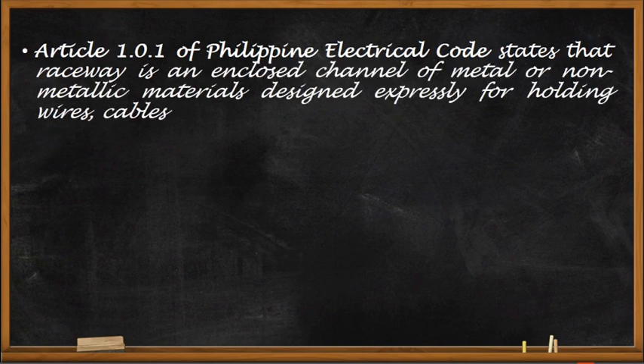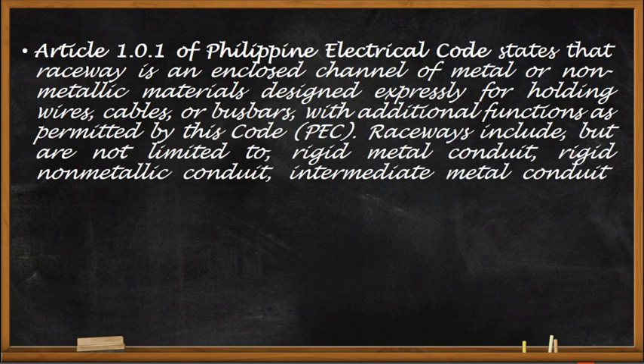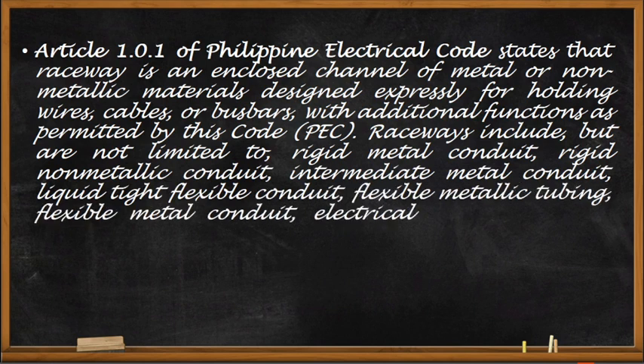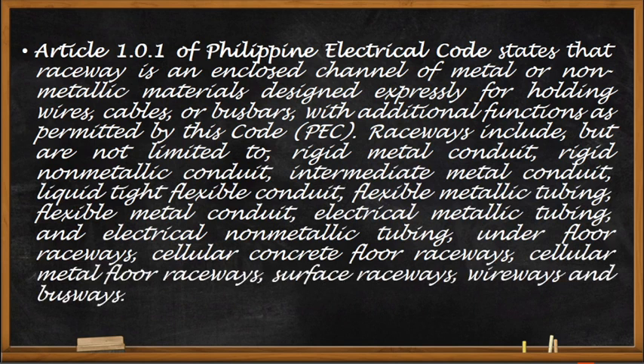According to Article 1.0.1 of the Philippine Electrical Code, a raceway is an enclosed channel of metal or non-metallic materials designed expressly for holding wires, cables, or bus bars with additional functions as permitted by this code. Raceways include but are not limited to rigid metal conduit, rigid non-metallic conduit, intermediate metal conduit, liquid-tight flexible conduit, flexible metallic tubing, flexible metal conduit, electrical metallic tubing, and electrical non-metallic tubing.